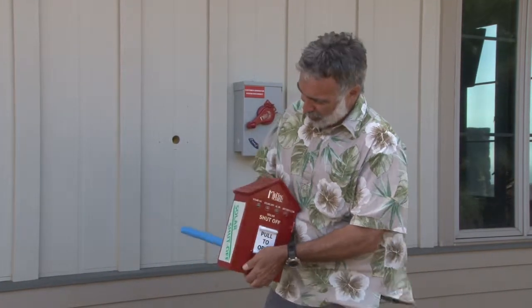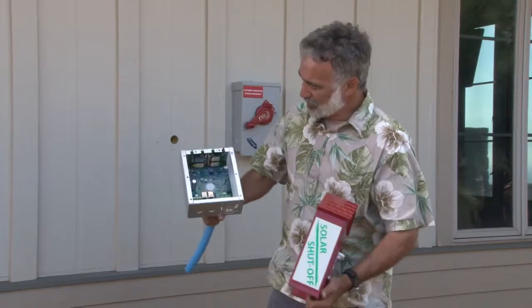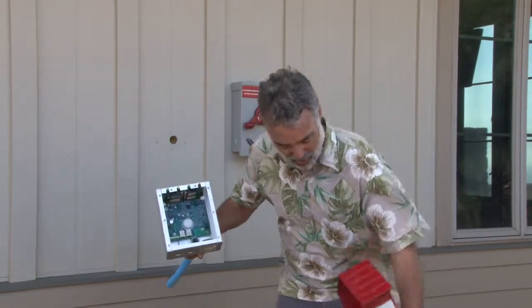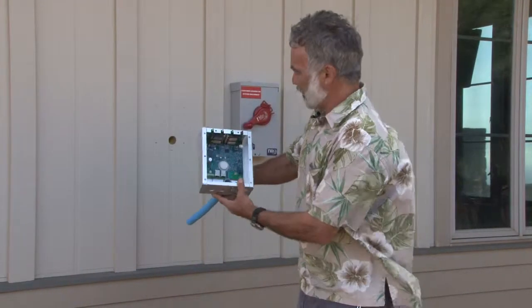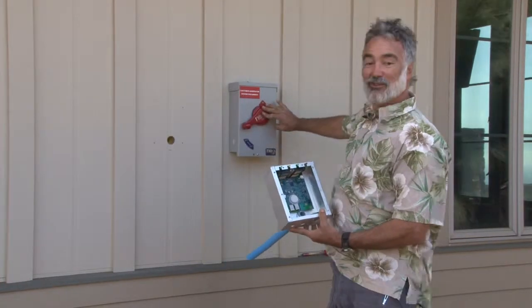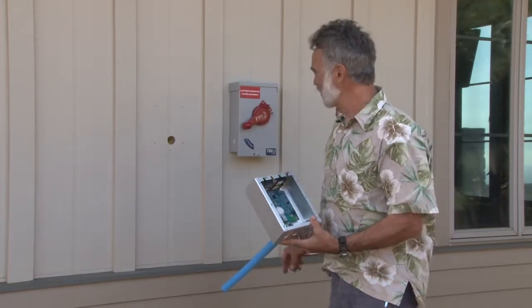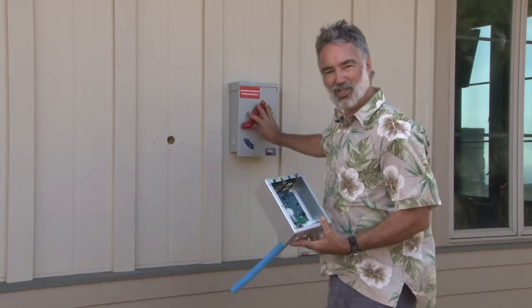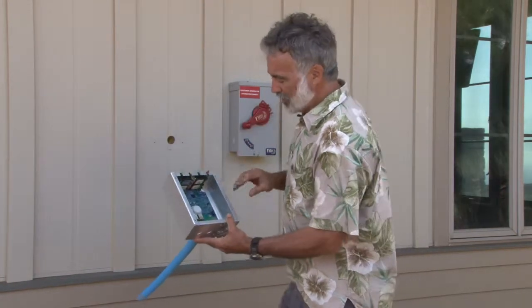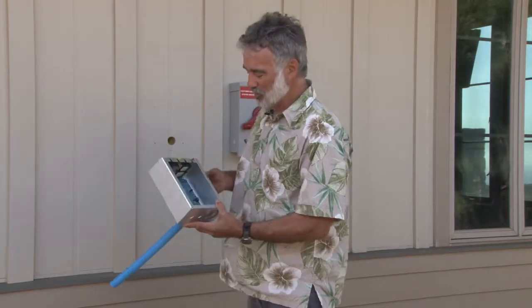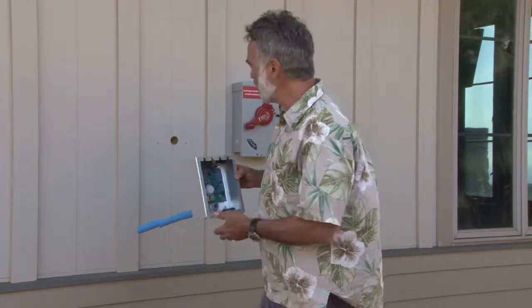So what we're going to do here is install the guts of the unit on the side of the building, next to our MNPV6 Disco micro version, which is the AC disconnect from the Fronius inverter. This is now going to interface with our DC disconnect, our MNDC4 that we just put up, and allow us to have a fully integrated safety system.